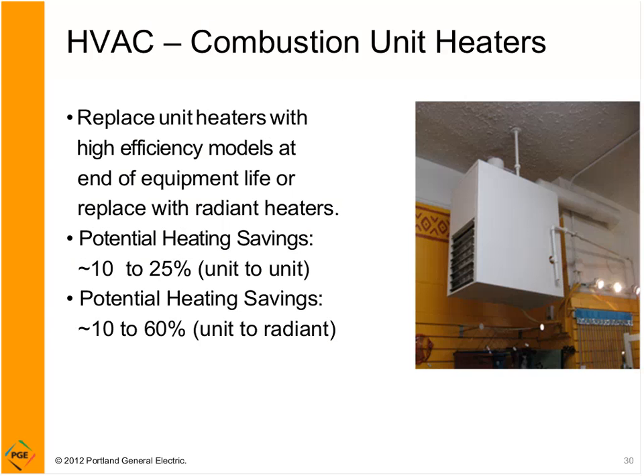So replacing these unit heaters with high efficiency models at end of equipment life, with either a more efficient unit or even radiant heaters. An example where a radiant heater may make sense would be, let's say, a warehouse. With the unit heater, you're heating all the space, and maybe you just have 1 or 2 people working there in the same area most of the day. You can have a radiant heater, which is basically just heating an object or the people under it, as opposed to heating the entire space. You can see some significant savings there. It doesn't work in all spaces, but when it can, a lot of potential savings. So potential heating savings are roughly 10 to 25% unit to unit. But if you have the potential to go to radiant, the savings can be a lot more significant, maybe 10 to 60%.